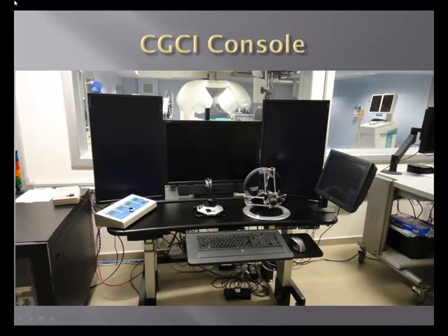We have a negative feedback algorithm, which we're not quite using yet, but it's part of our intellectual property, where eventually, if you're up against the wall, you will have increasing resistance against the joystick up to the point that you will not be able to move it, so that you can minimize the amount of potential damage you can do. We have another joystick here in the current way we have the system built, which allows us to also rotate the image, and also allows us to give slack or pull back slack. So we're basically working with two hands sitting here at the joystick.